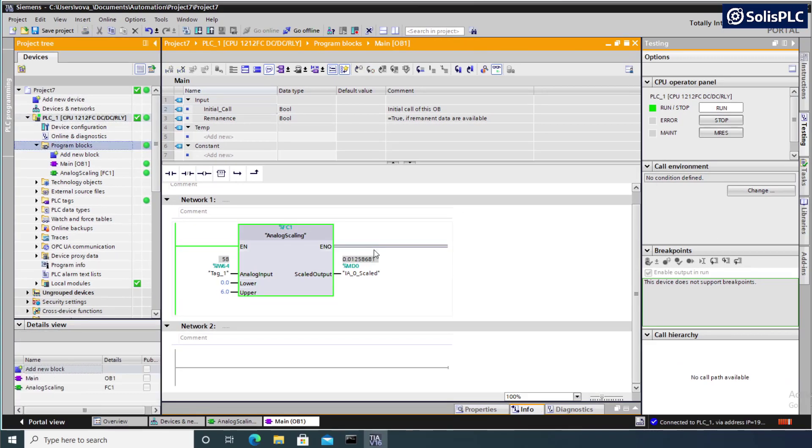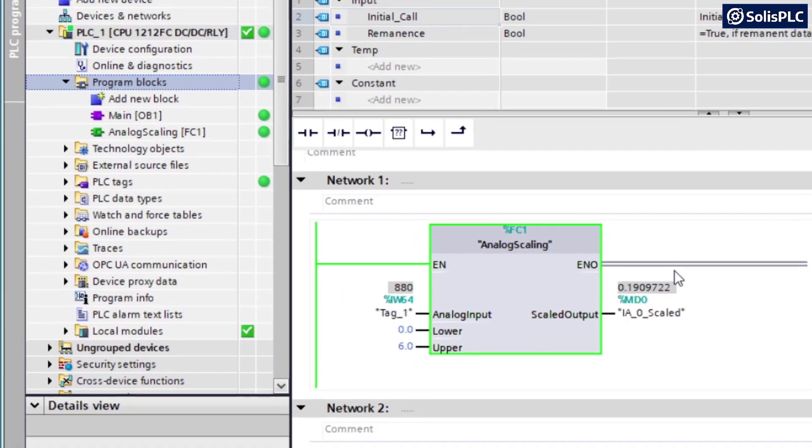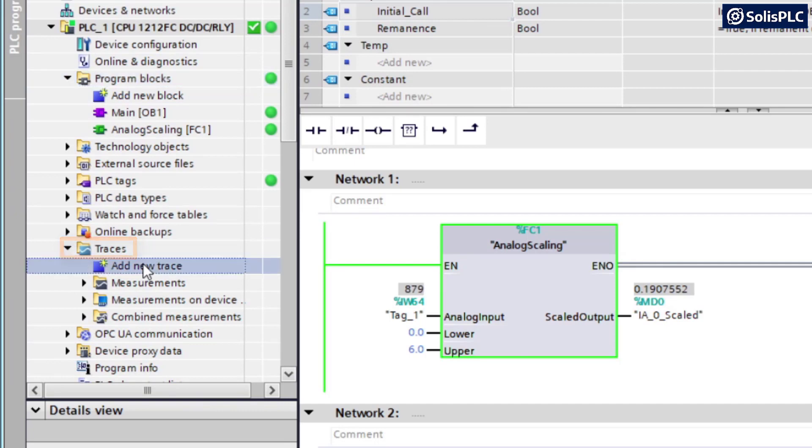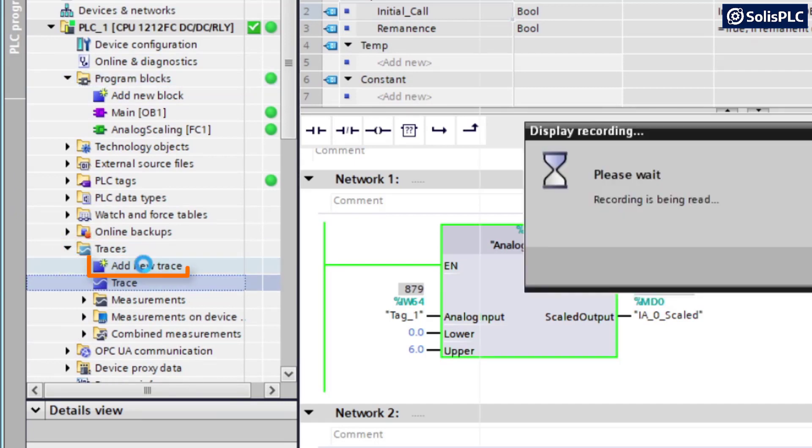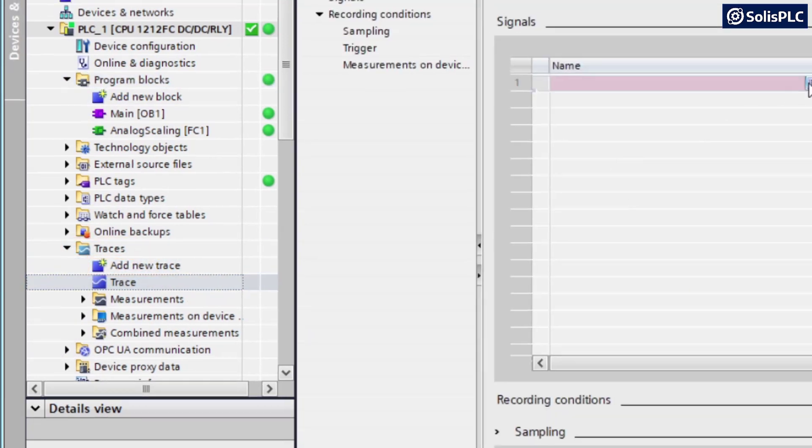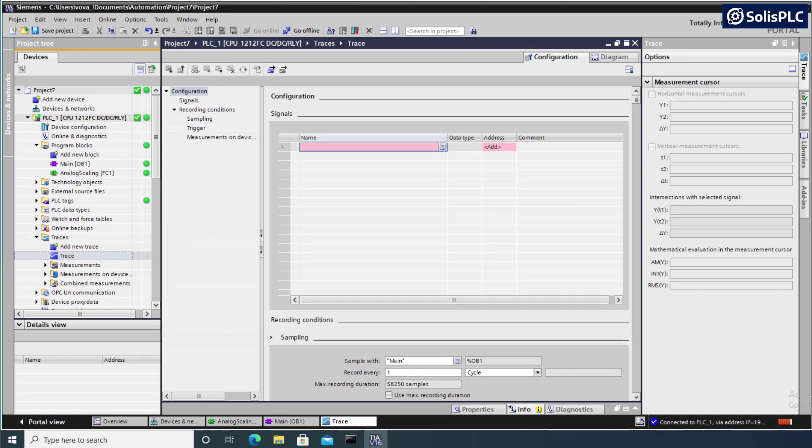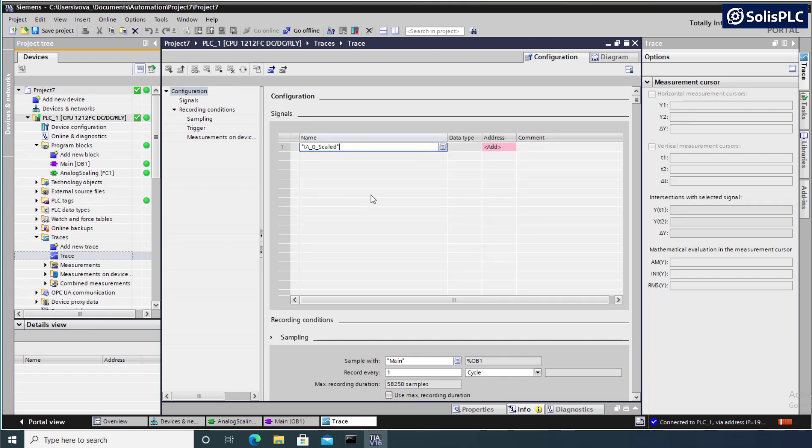A very important feature in TIA Portal that allows us to troubleshoot analog signals is called tracing. So we can go into traces and we can add a new trace, which is going to allow us to select a number of tags that we want to monitor. So here, since I only have one tag, I'm going to click on this little icon and I'm going to select a tag that we've just created using our scaling function.